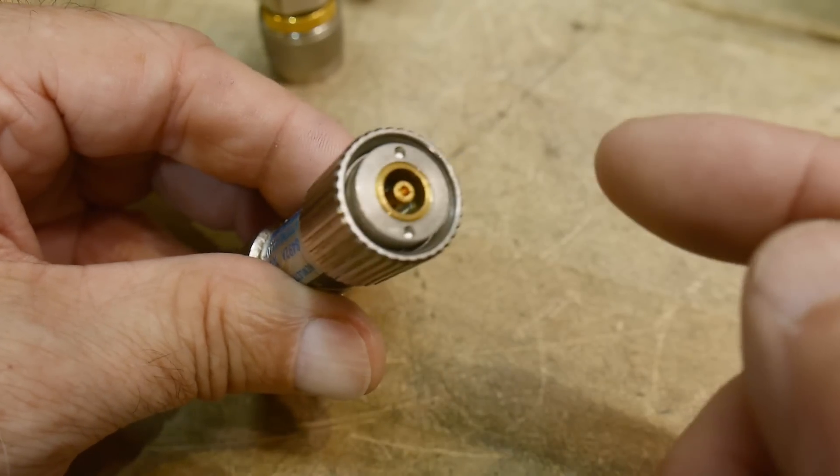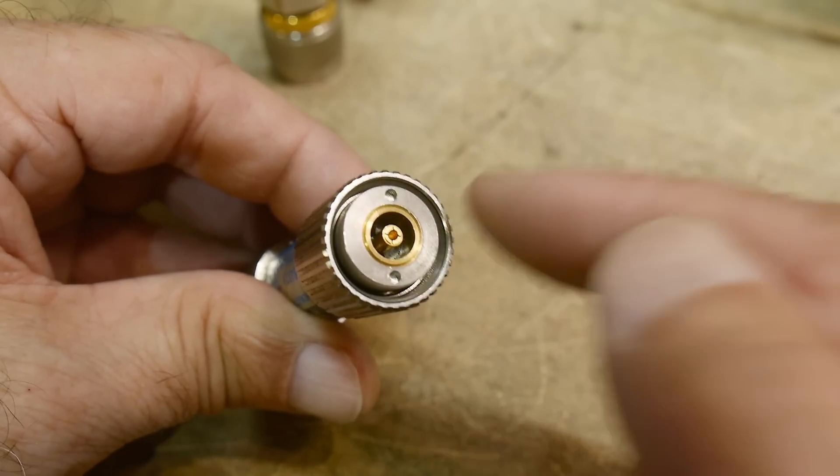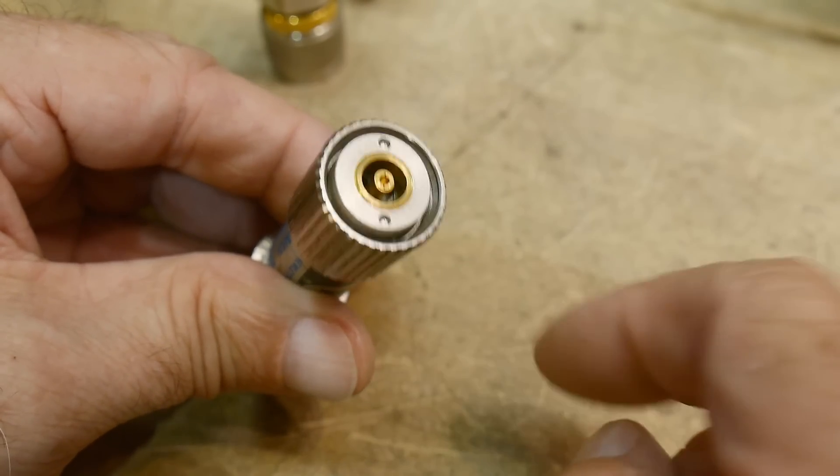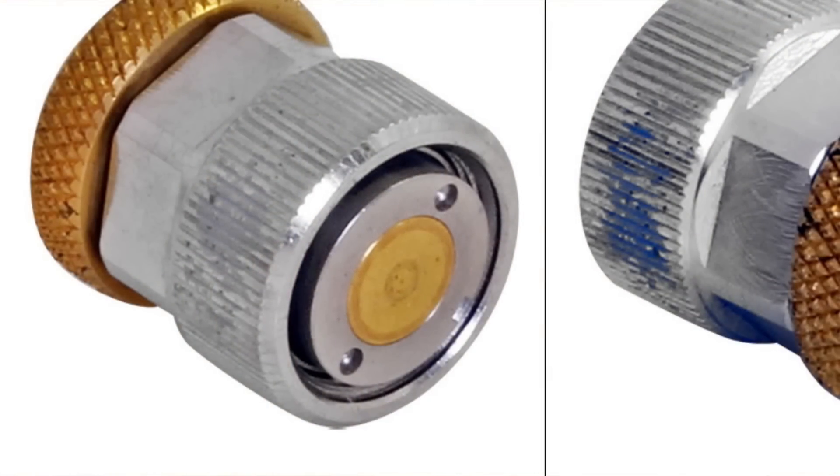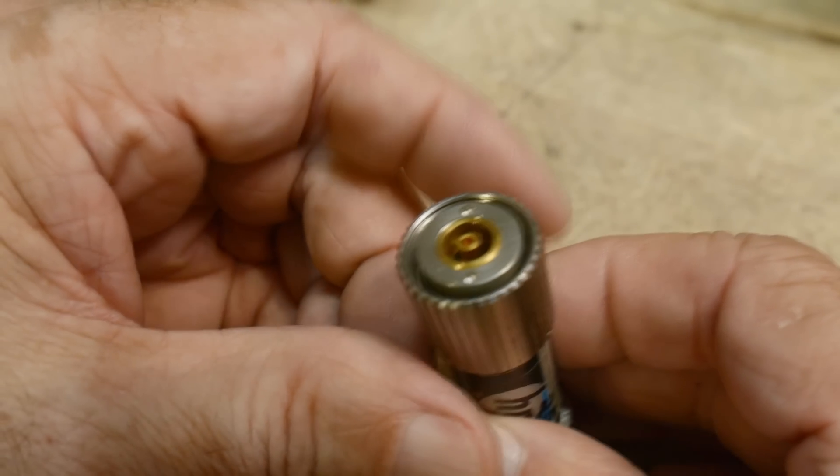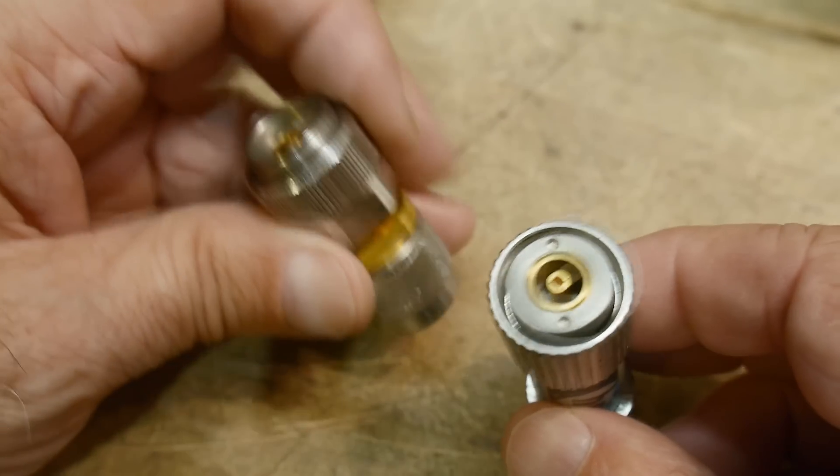Well, these have a plane, these have a real plane, right? They have a very, very distinct plane, and so the open short cals look very, very easy. The short is just a piece of metal, and this thing just butts up against this copper slug, or gold-plated copper slug. And then the open is just a tube, and so you can really understand that there is a plane of reference, and it can be very, very, very accurate, because it's machined very accurately. So that's why these things sort of got invented.